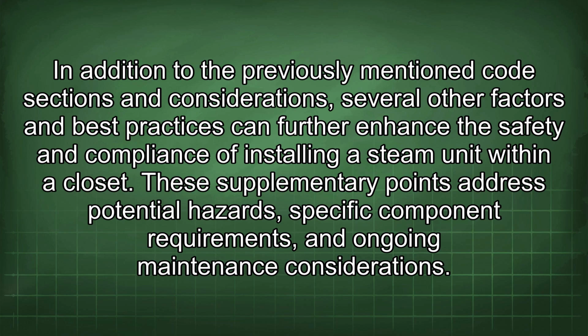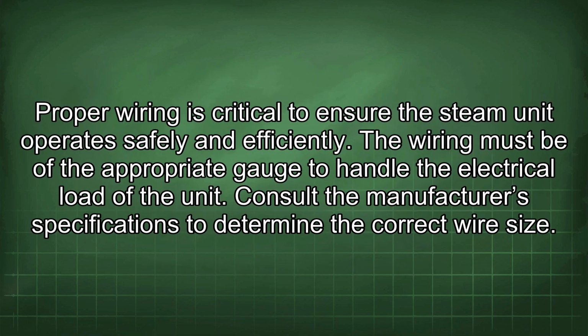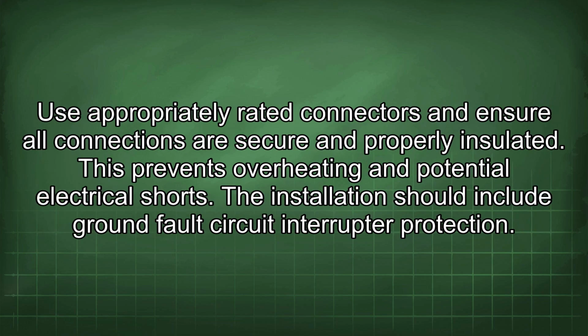In addition to the previously mentioned code sections and considerations, several other factors and best practices can further enhance the safety and compliance of installing a steam unit within a closet. These supplementary points address potential hazards, specific component requirements, and ongoing maintenance considerations. Proper wiring is critical to ensure the steam units operate safely and efficiently. The wiring must be of the appropriate gauge to handle the electrical load of the unit. Consult the manufacturer's specifications to determine the correct wire size. Use appropriately rated connectors and ensure all connections are secure and properly insulated. This prevents overheating and potential electrical shorts.